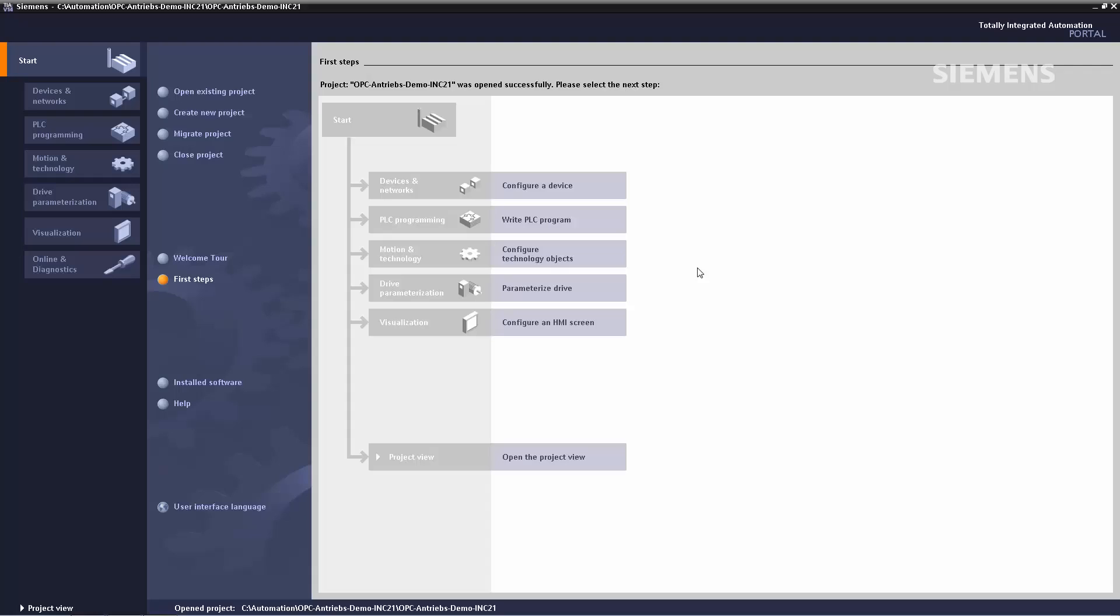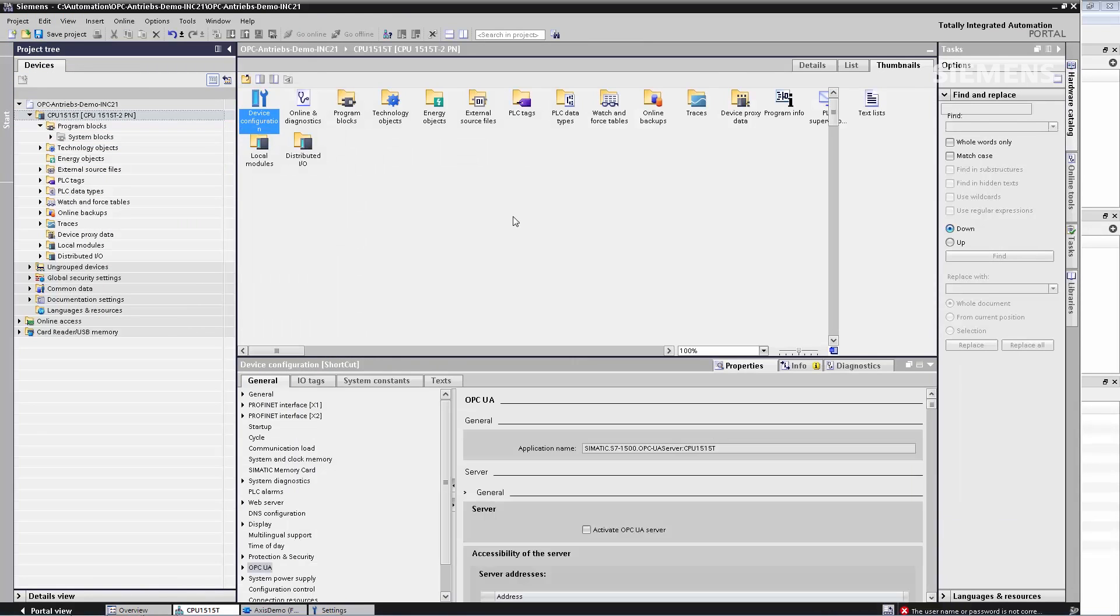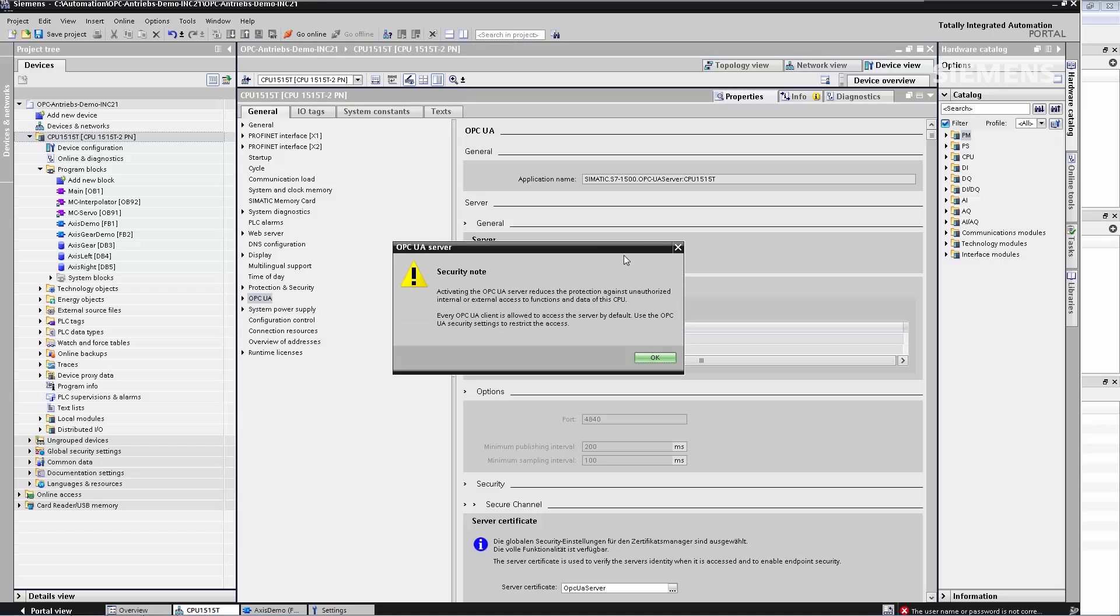And now I'm going to show you everything in practice. As you can see, I've already opened the project and in step one, I switch over to the hardware properties of the CPU. I can see the CPU here and I maximize the hardware properties dialog. I find a new entry in the hierarchy OPC UA. Here I can activate the OPC UA server with one click.